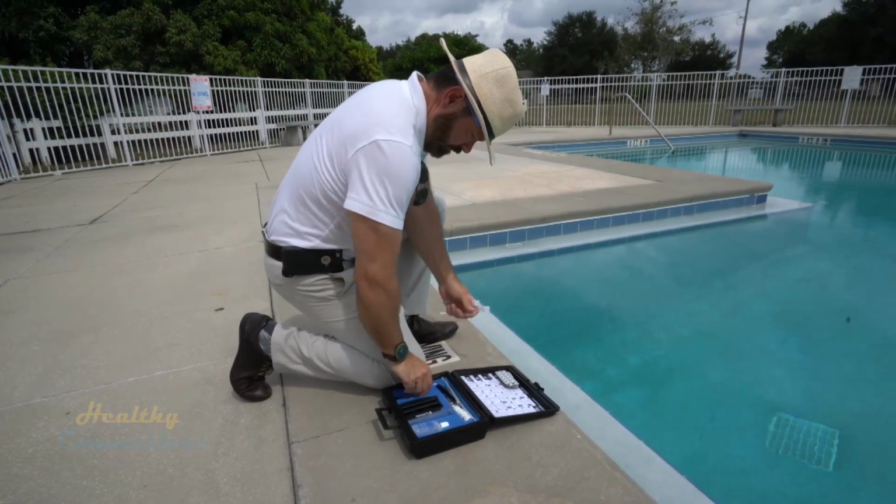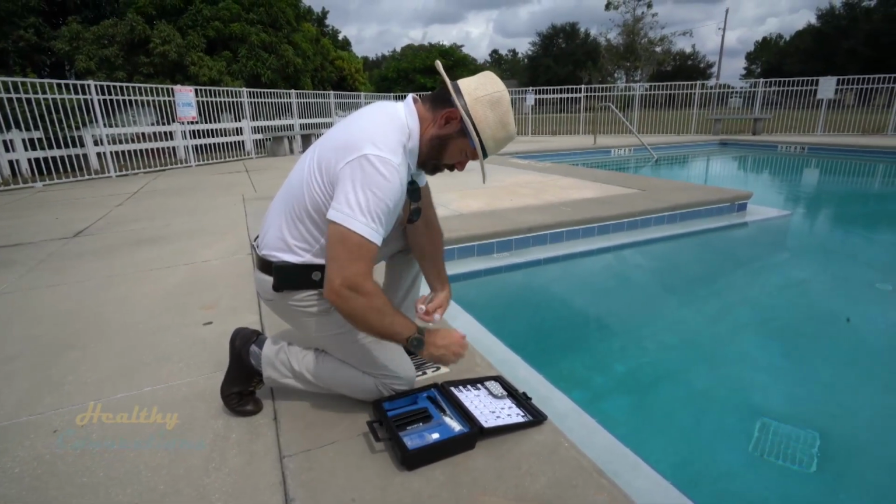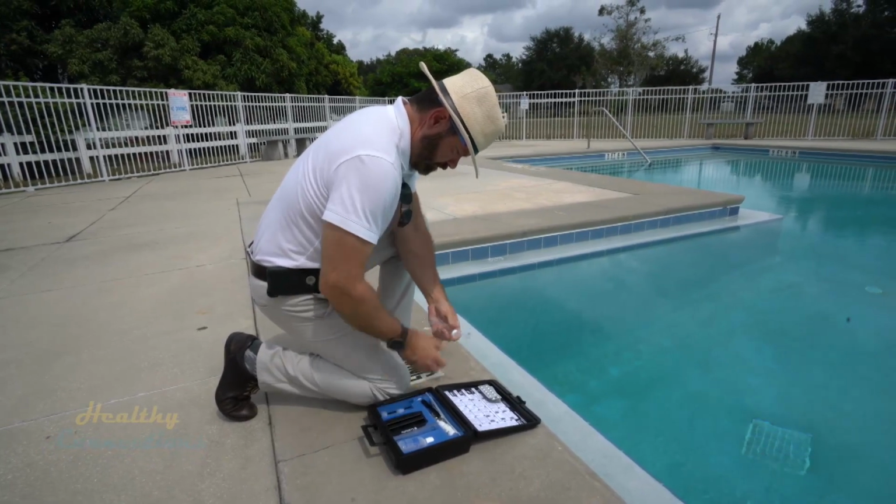Like sometimes gaskets go on these pumps. Chlorine is in the water. It really messes with the substrate or whatever it's made out of. It corrodes. So pumps don't last a long time sometimes just because chlorine is so corrosive. But we don't want any leaks and stuff like that, and we want to make sure the pump is actually being able to get the GPM flow.